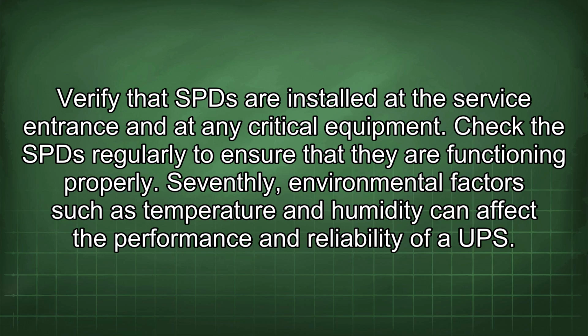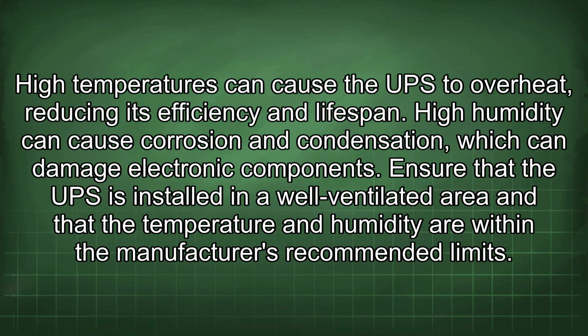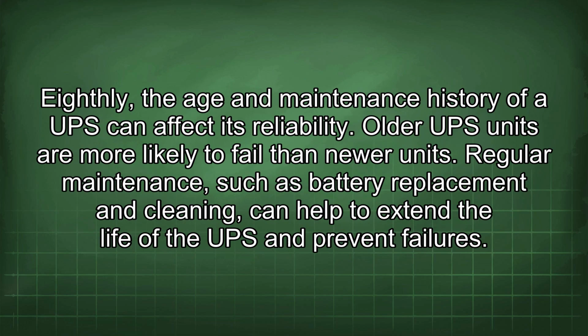Seventhly, environmental factors such as temperature and humidity can affect the performance and reliability of a UPS. High temperatures can cause the UPS to overheat, reducing its efficiency and lifespan. High humidity can cause corrosion and condensation, which can damage electronic components. Ensure that the UPS is installed in a well-ventilated area and that the temperature and humidity are within the manufacturer's recommended limits.